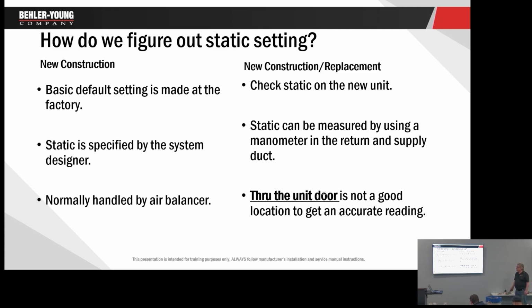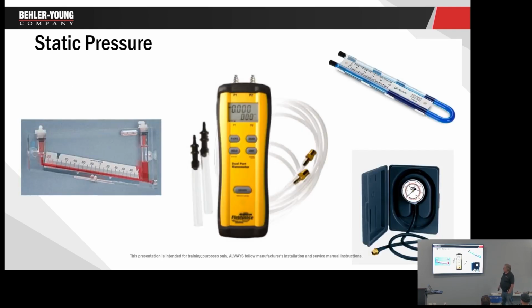It's actually pretty simple. New construction, right? Well, the engineer says he designed this duct system to 1 inch of static, right? Do we trust that? No. No, because we know it never went in the way it was designed. So we have to actually check it. Could I check the old unit? No, because again, it doesn't matter. That was the old blower, whatever CFM it was moving, we don't know. So we're going to get our manometer.